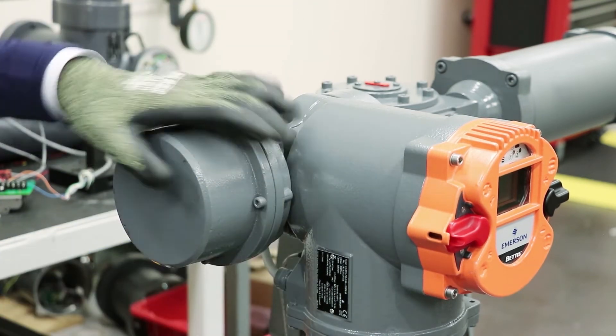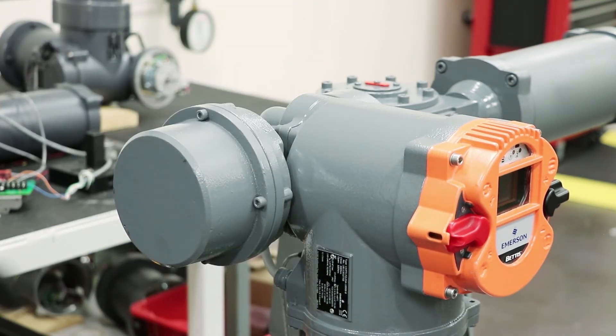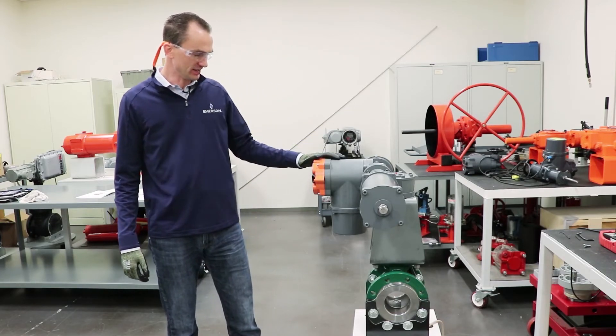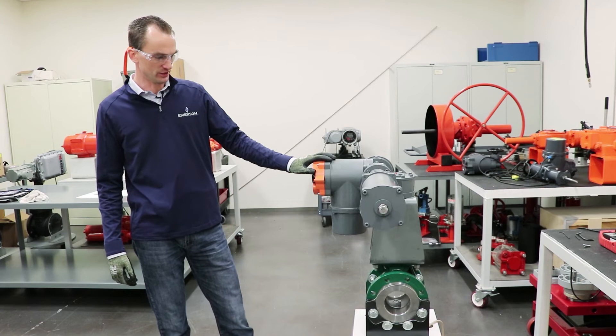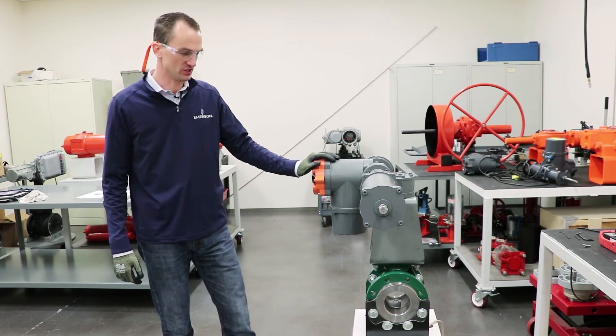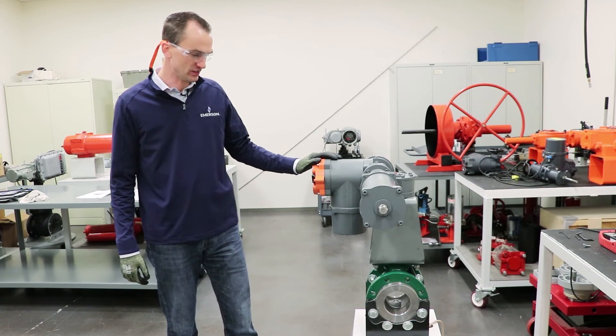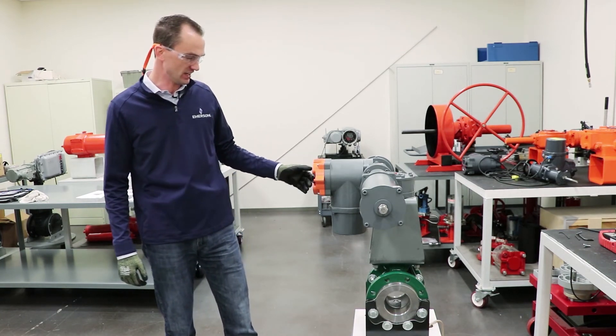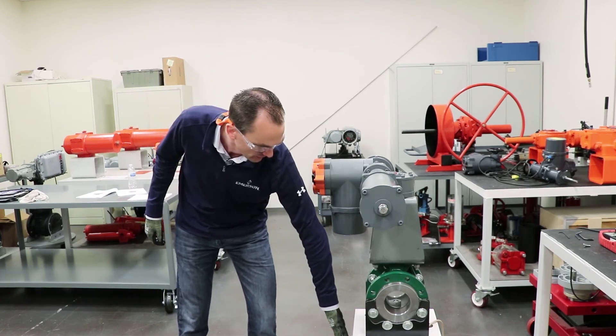We got the cover back on and now we'll demonstrate the failsafe functionality with the setting at the highest speed. The brake cover is fully assembled back on the actuator, power is back on, and we have the valve and actuator in the fully open position. So now you'll see the failsafe speed at that top end of the range for the RTS. Once we kill power...